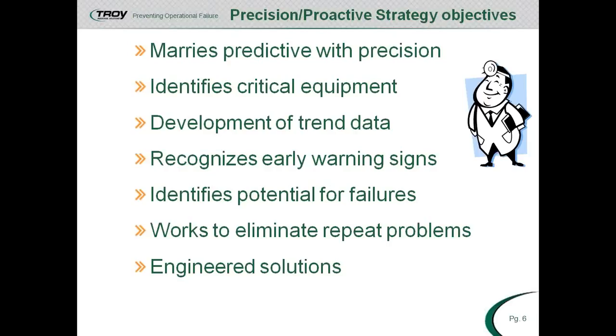Some equipment, like we said, it's still cost effective to run to failure. In some cases, people still blend preventative maintenance, but we're finding that the precision proactive strategy, and I'll give you a case study later, is really starting to pay off for folks. The third entry here is the development of trend data. If you can imagine, we're reading vibration analysis figures or current figures on a motor, and we are seeing the same readings time after time. And later on in the year, in the fall, all of a sudden we see large increases, and the trending data goes up. It's going to give us the ability to recognize early warning signs.